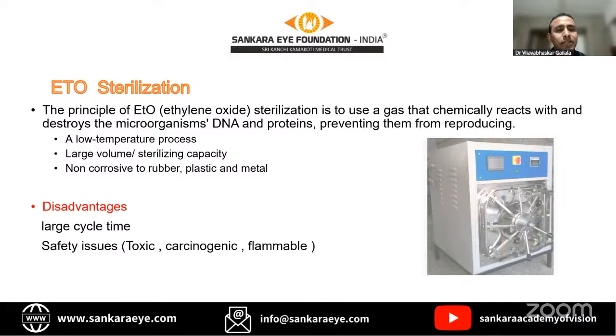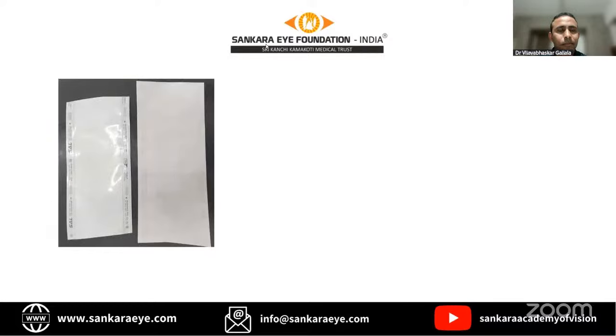But there are some disadvantages. First thing is it's a long cycle. Usually the autoclave will finish within 20 minutes, but in ETO, we need a minimum of 12 to 14 hours for the completion of the cycle. And the main important thing is the safety issue. This gas is toxic and carcinogenic to persons, and it's highly flammable. And one more thing is for the setup of this ETO equipment, we need a separate structure. It should be on the top floor of the building. And the packing for ETO is totally different from moist heat sterilization. In this ETO packing, one side is a transparent cover, the other is a porous sheet, which allows the transfer of this gas while preventing microorganism entry.